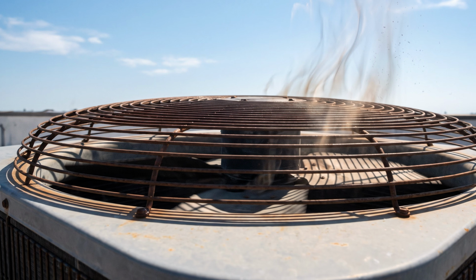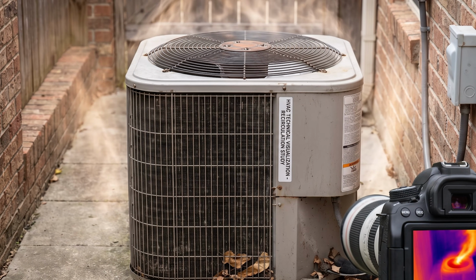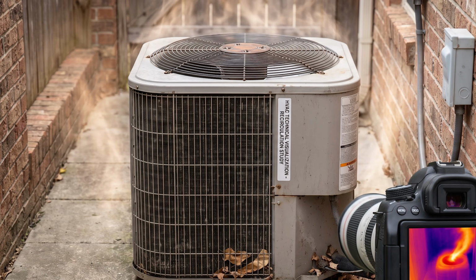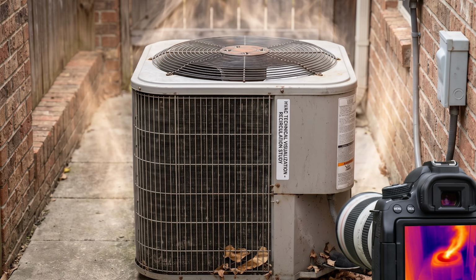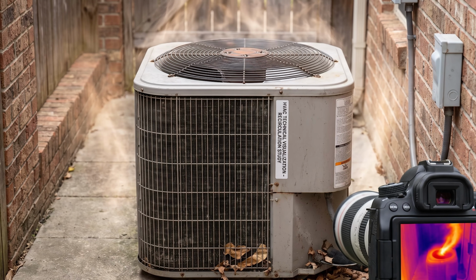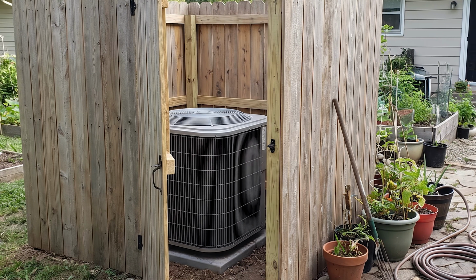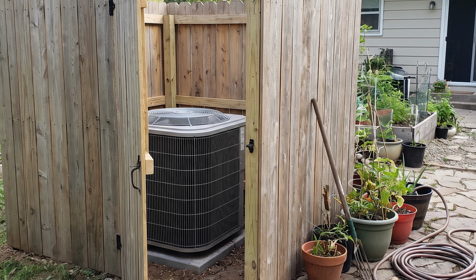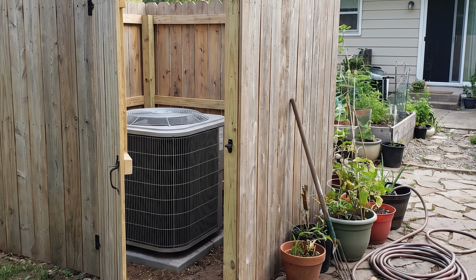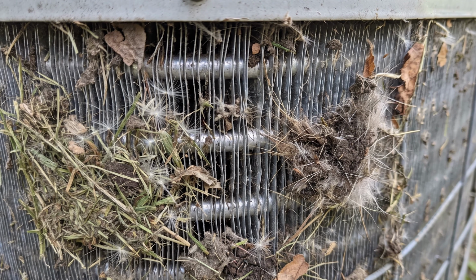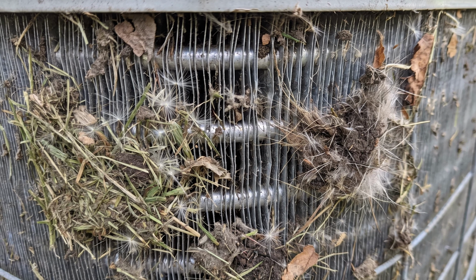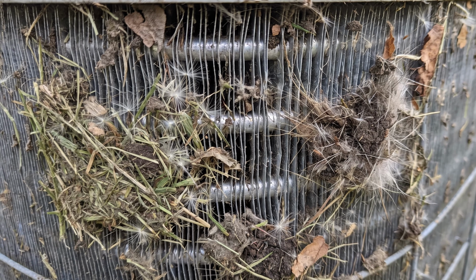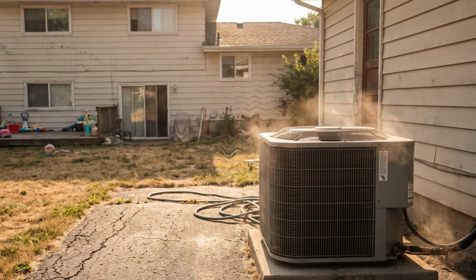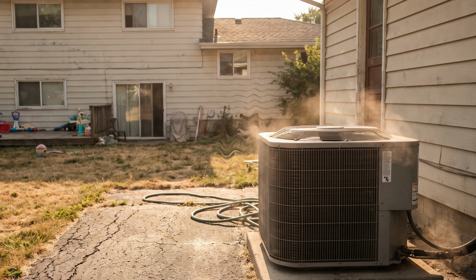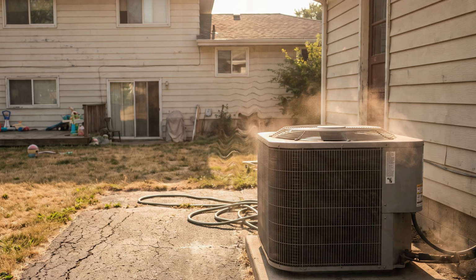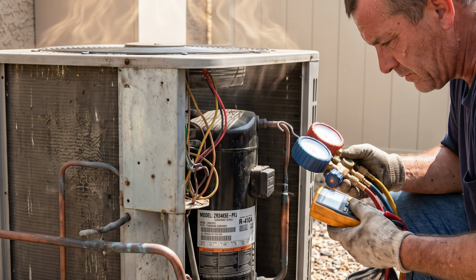But people think the metal box is ugly. They don't want to look at it while they're grilling on the patio, so they build solid wooden fences directly around it, or they plant thick bushes right up against the metal panels. When you block the sides of the condenser, the heat cannot escape. The machine ends up sucking in its own exhausted hot air. The compressor, which is the heart of the entire system, begins to run hotter and hotter. Eventually, the oil inside the compressor breaks down. The internal parts grind together and the unit dies. A new compressor often costs upwards of $2,000 and usually means replacing the entire outdoor unit.